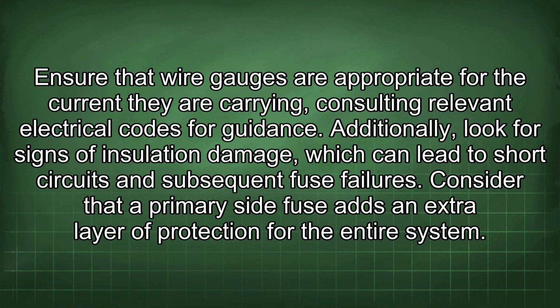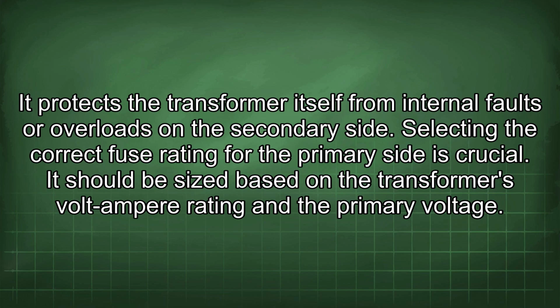Consider that a primary side fuse adds an extra layer of protection for the entire system. It protects the transformer itself from internal faults or overloads on the secondary side. Selecting the correct fuse rating for the primary side is crucial. It should be sized based on the transformer's volt-ampere rating and the primary voltage.